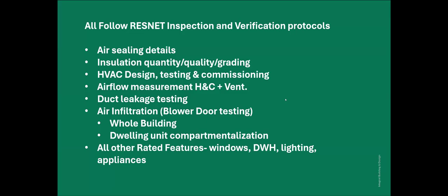Post-construction, airflow measurement and air balancing for the heating, cooling, and ventilation systems need to be conducted. I mentioned duct leakage testing already, and there are performance targets for that, as well as the blower door test, which everybody seems to focus on.